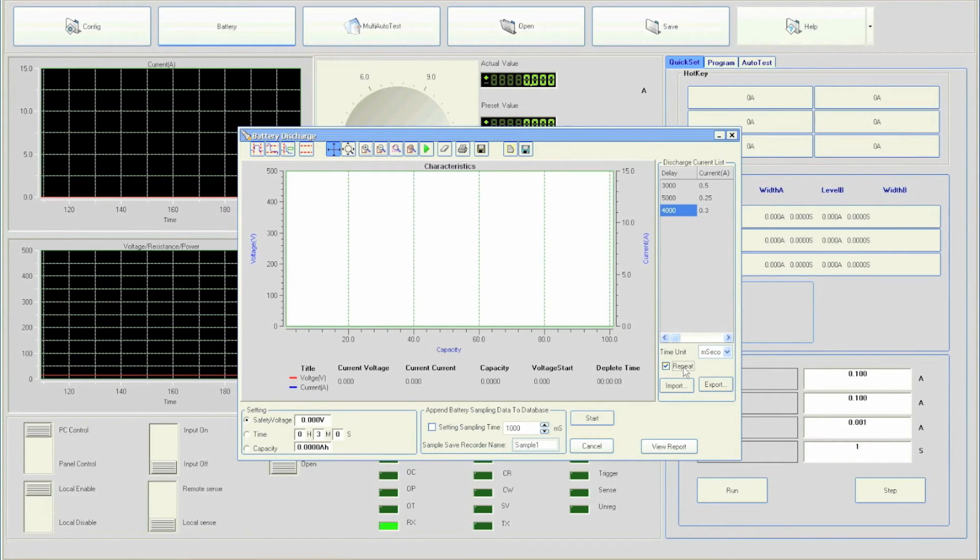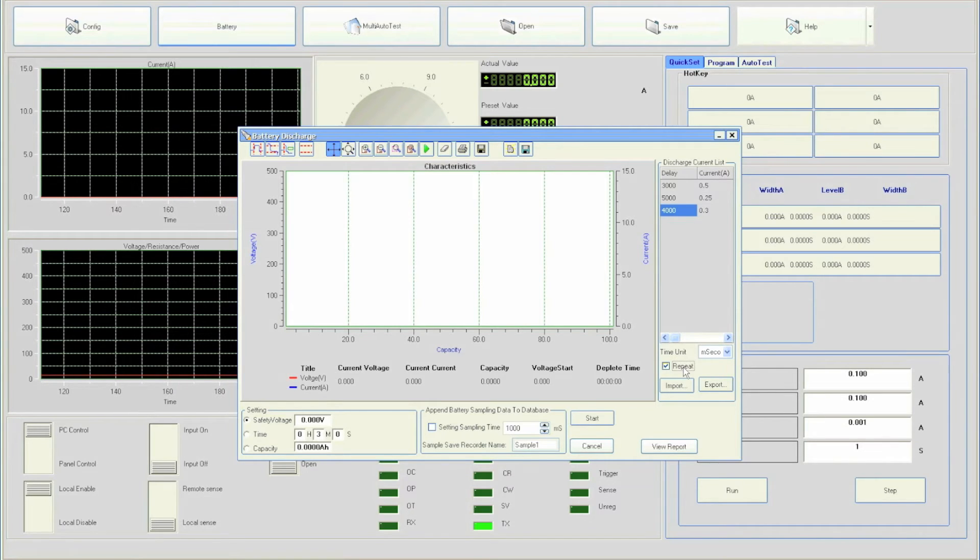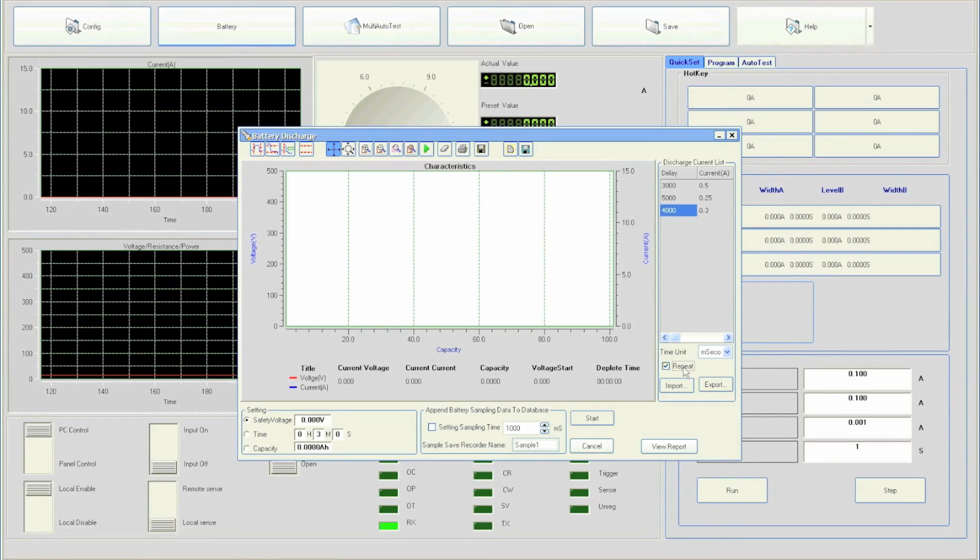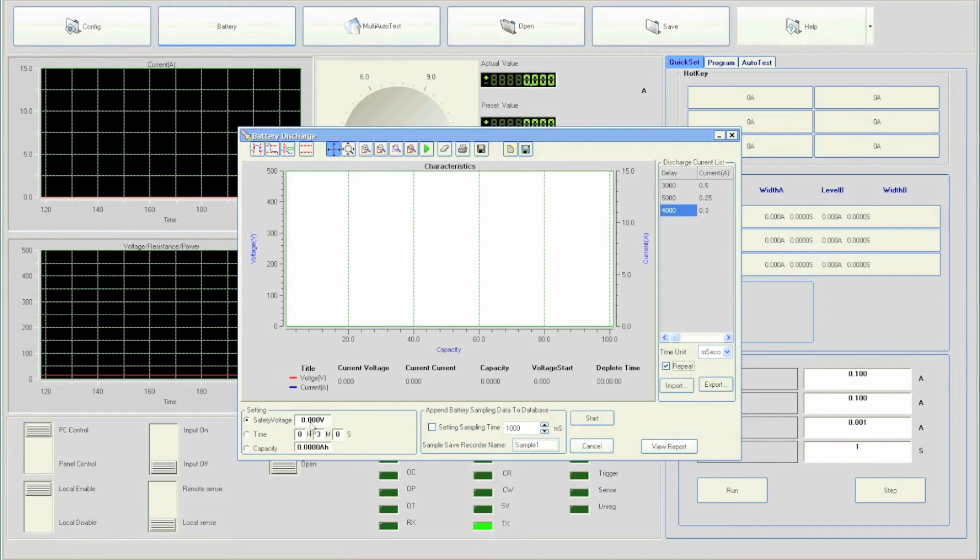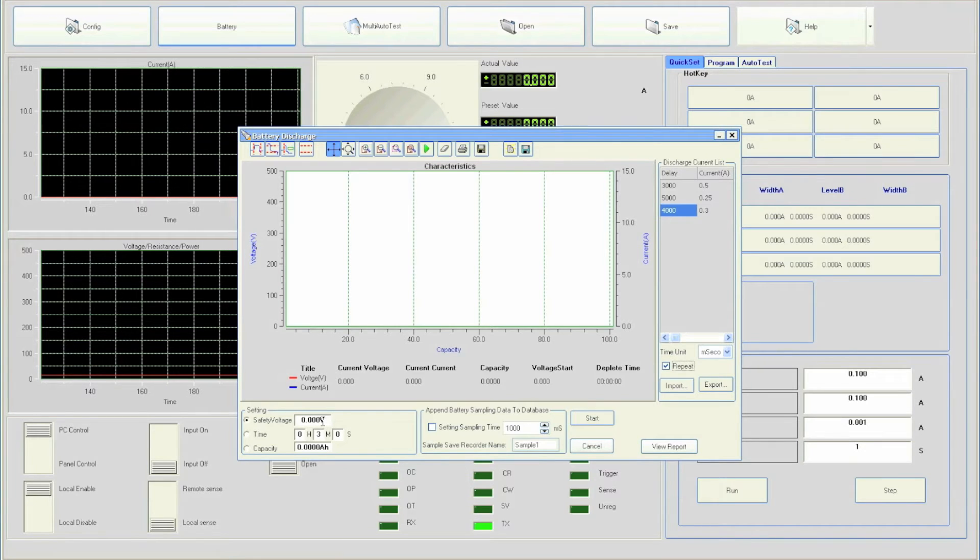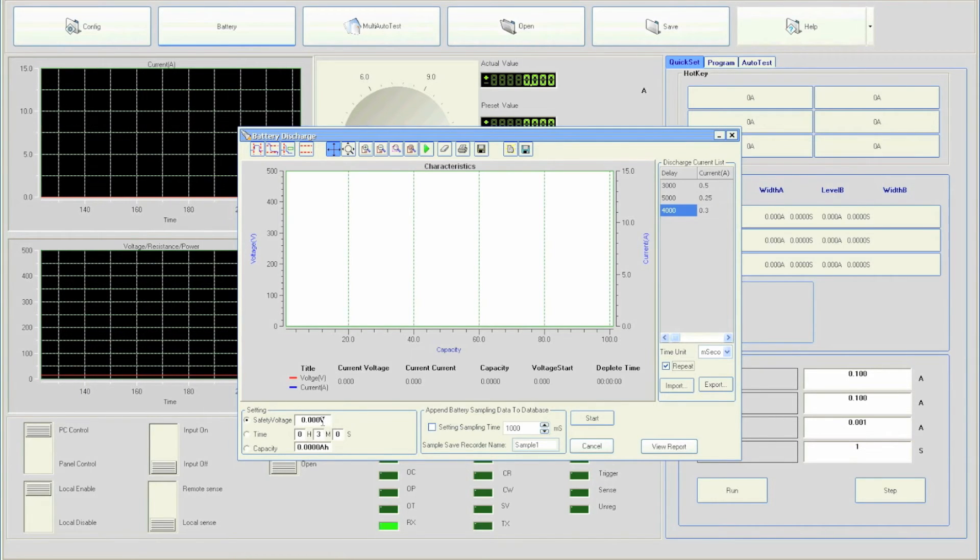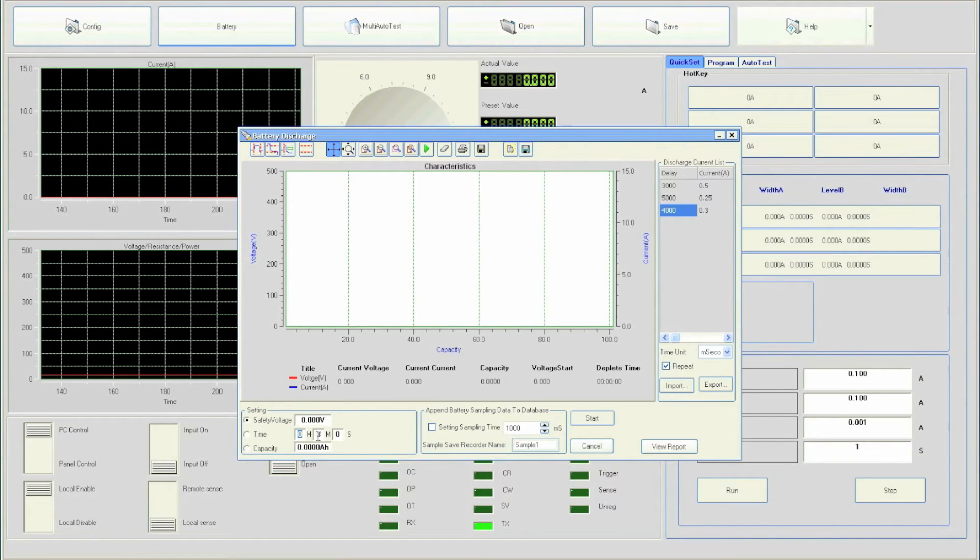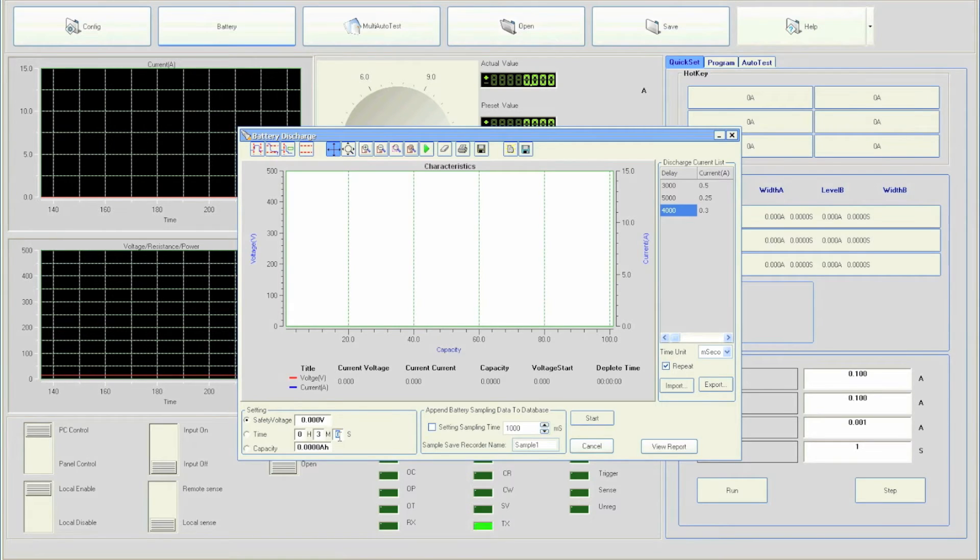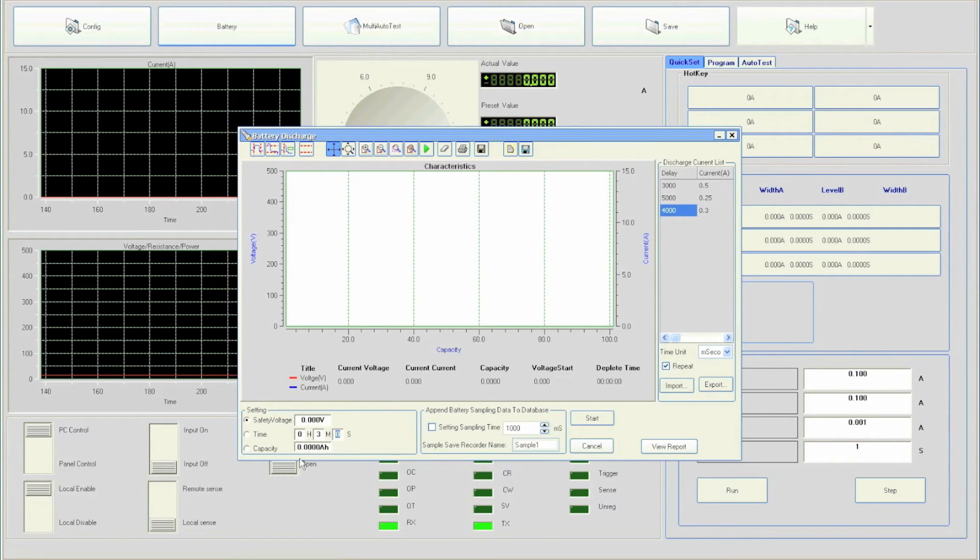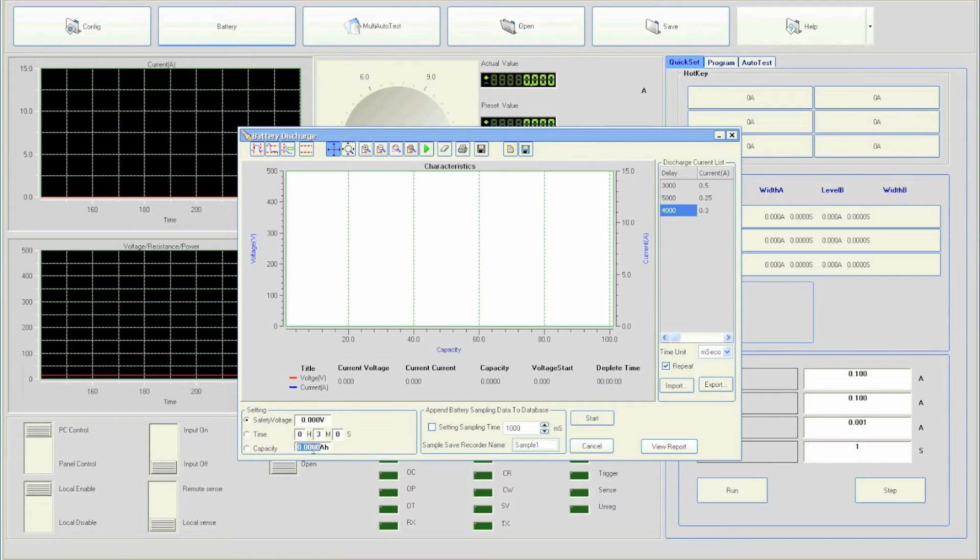The software gives user the option to select how the test will be run. Users can run the test based on safety voltage or threshold voltage similar to the internal battery test demonstrated earlier. Next option is to specify a specific amount of time to run the test. Users can enter hours, minutes, and seconds. Lastly, users can run the test based on a certain capacity. Once capacity is reached, test will end.